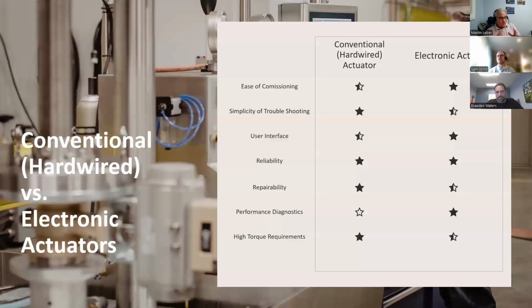Now, simplicity of troubleshooting—unless you're really experienced with the electronic type, know the symptoms, and can read between what it's telling you and the experience you've had repairing these things, it may not be the easiest. However, when you troubleshoot a basic hardwired actuator, you just need a multimeter. You probe it, follow the signal through, and can quickly find out where the fault is.